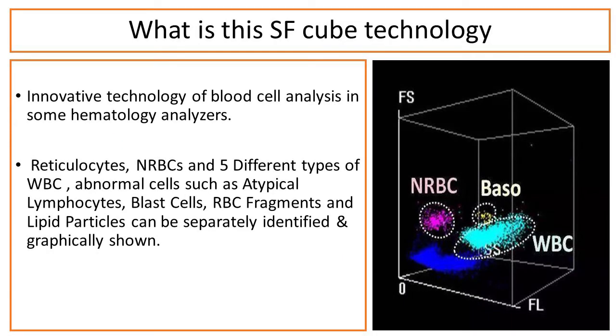What is SF Cube technology? The SF Cube method is an innovative technology of blood cell analysis used in hematology analyzers. In this method, reticulocytes, NRBCs, and five different types of WBC abnormal cells — such as atypical lymphocytes and blast cells — as well as RBC fragments and lipid particles can be separately identified and graphically shown in a 3D scattergram.